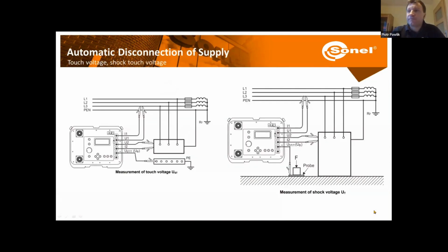Okay, now further on, if we are using our top models, like MZC 310, 320, or 330, the fault loop impedance meters, then besides checking the value of the impedance of fault loop or calculating the fault current, we can also check the touch voltage and the shock touch voltage. So those will be the voltages between the cover of our device and the main grounding rail or actual earth. So in theory, this value should be 0. In practice, we can have some single volts, but in case we have some faulty construction of our electrical network, then we can expect some higher values of voltages. If we find those, then we need to check the construction of our network and find where the problems are.